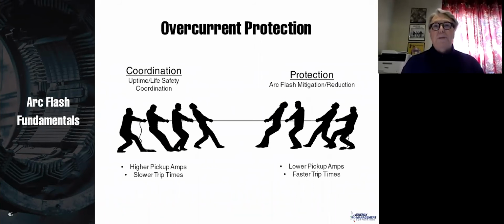Okay, overcurrent protection is a trade-off with coordination. In order to get the best coordination, we generally want to have time delays on the upstream breakers. Whenever you put time delays on the upstream breakers, then you make the circuit more dangerous. And as most people can tell you who have been in arc flash studies for a while, the actual arc flash current tends to be less important than the time it takes to interrupt that current.